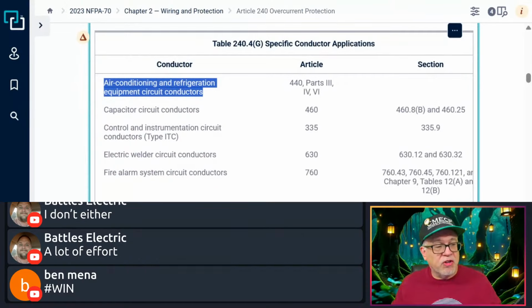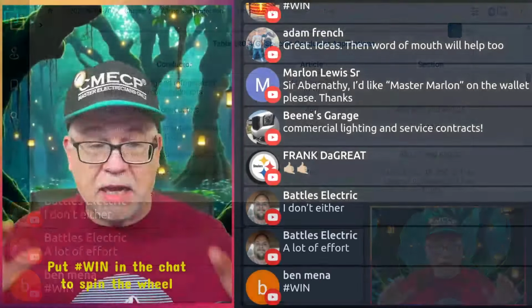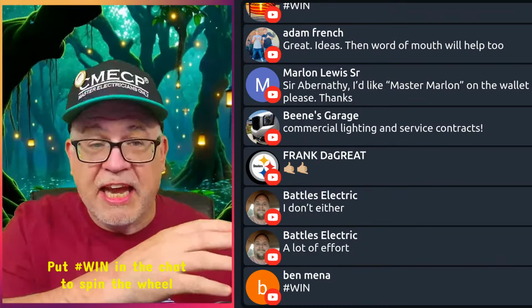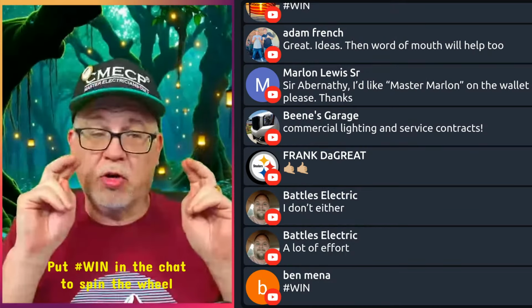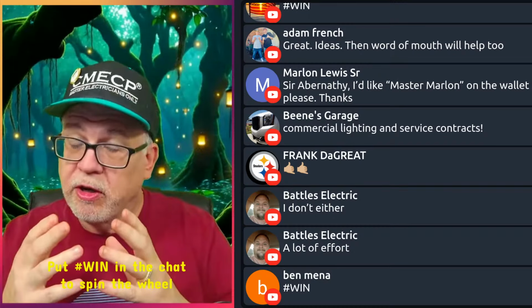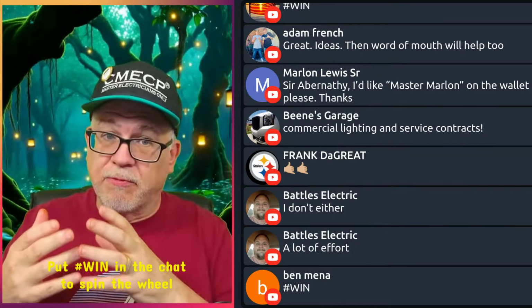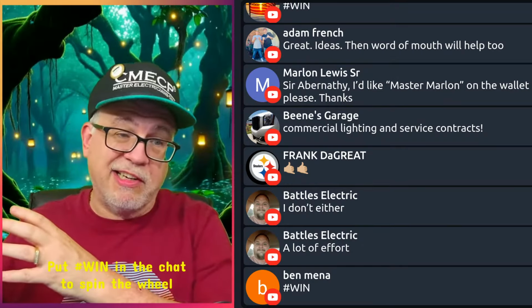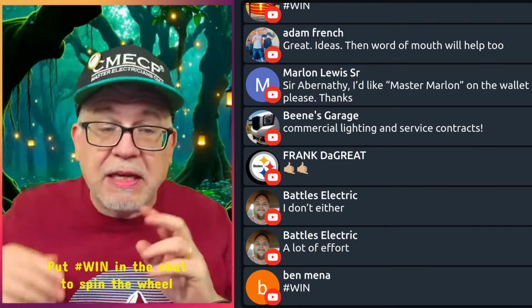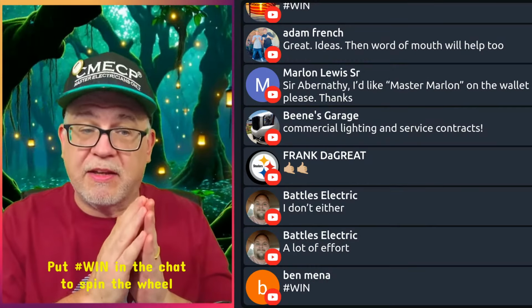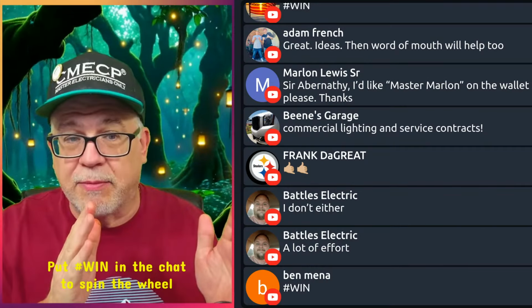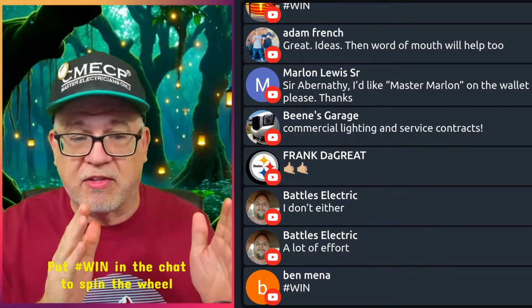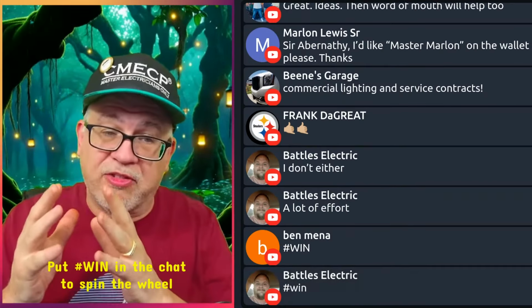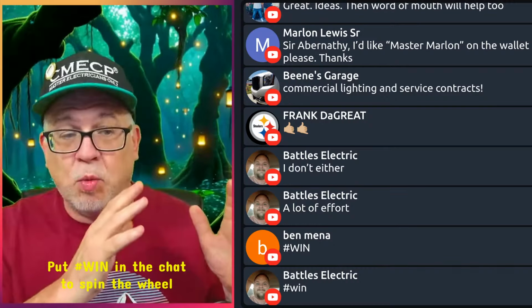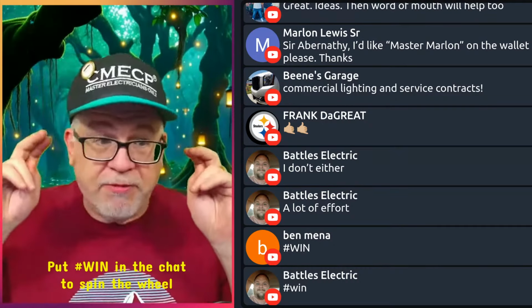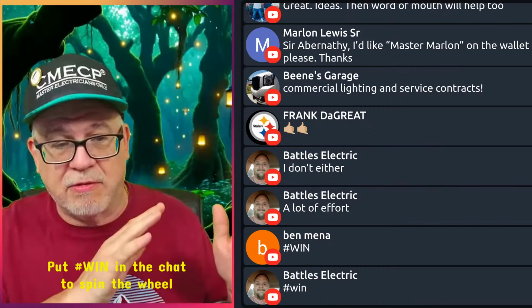Okay, now, just so you know this, for giggle time, if I'm running non-metallic sheath cable to that disconnect on the interior portion, and then I'm switching over to THHN, THWN from the disconnect down to the actual air conditioning unit, then remember that I am going to be limited to the 60 degree because of the weakest length. And that is the fact that that non-metallic sheath cable is only rated for ampacity under the 60 degree column. So no matter what I switch to outside, it's irrelevant because I chose a weaker rated product, not an inferior product, just weaker as far as ampacity rated based on the table.